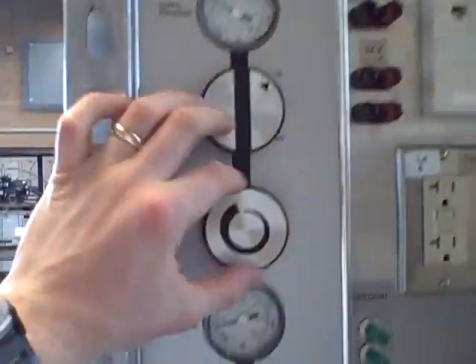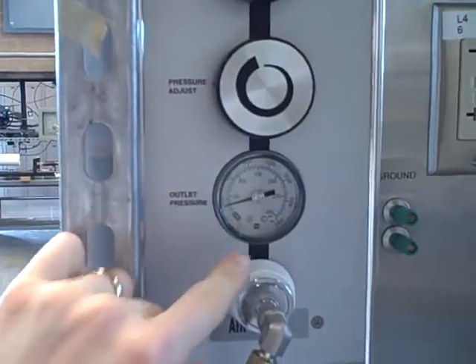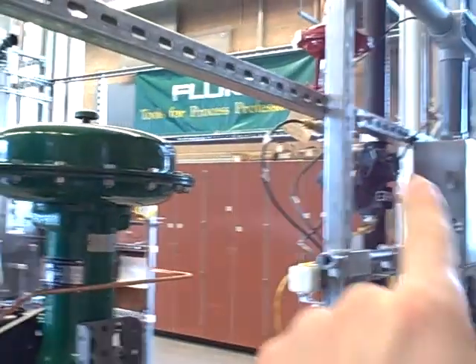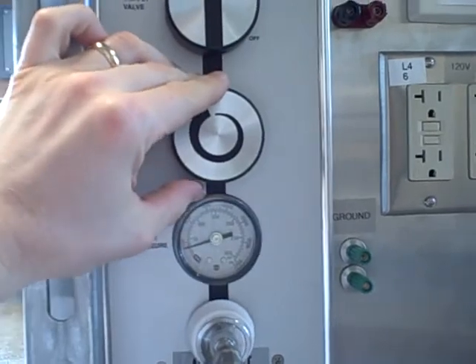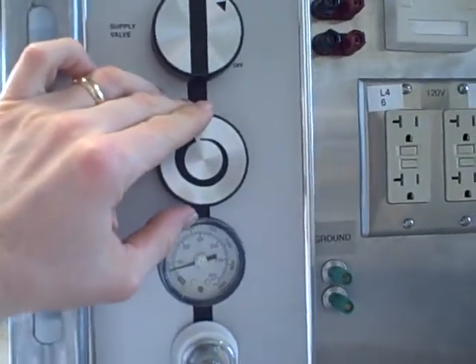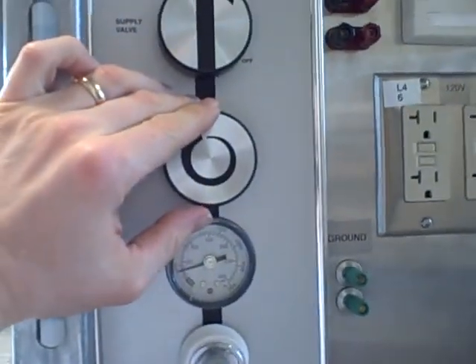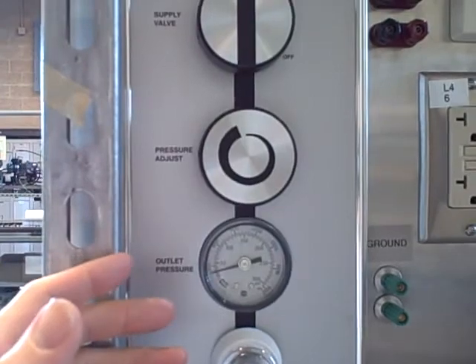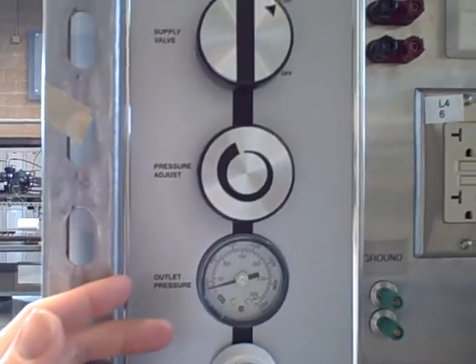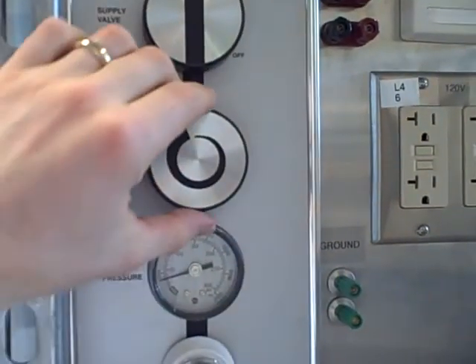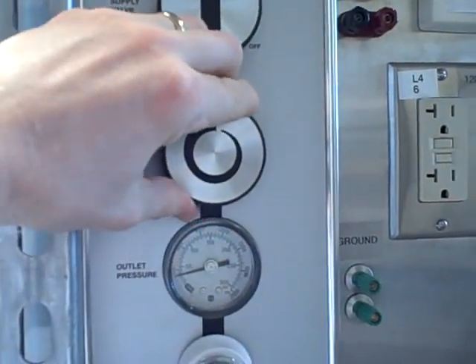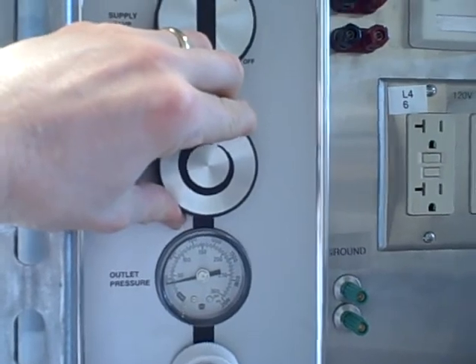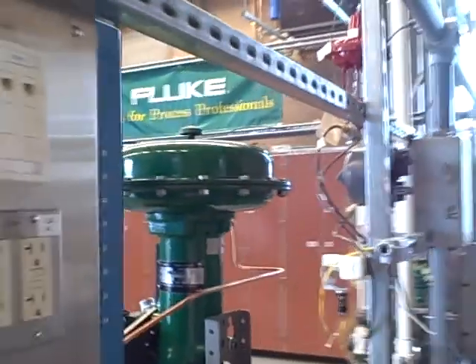For example, over here, I have a variable air pressure. I can turn up or turn down. And this air pressure is my supply pressure to my turbine. So obviously, if I turn the air pressure up, that gives a higher gain to the system. Now the same amount of control valve motion will have a greater influence on turbine speed than it did before. I can do that right now, turning the air pressure up. You can hear the turbine increase speed, but then the control system kicks in and tries to regulate the speed at the setpoint.